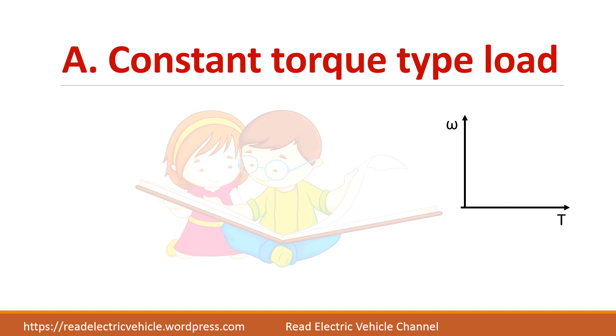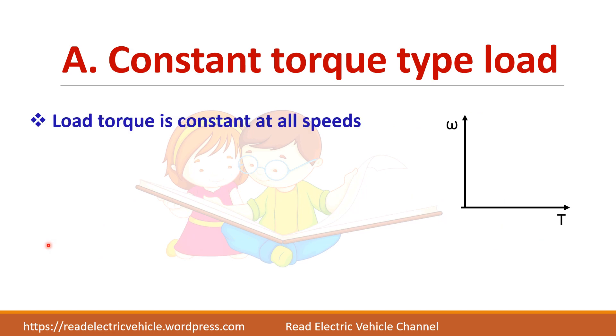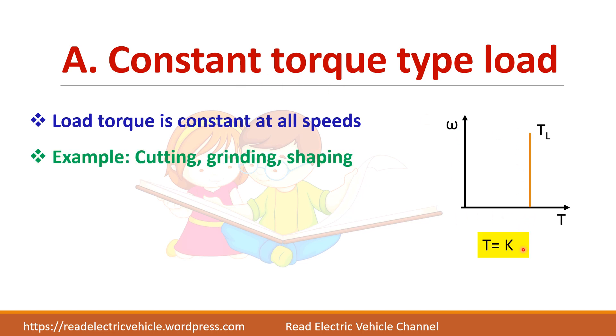The first type is constant torque load. As the name says, torque is constant at all speeds. This type of load is found in cutting, grinding, and shaping machines, as well as in low-speed hoists — machines that move loads between lower and higher levels.